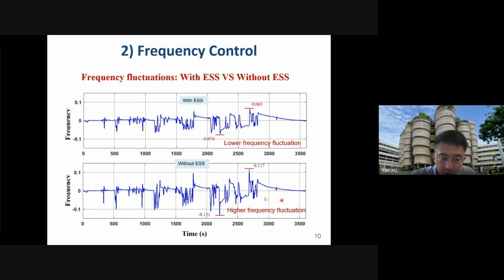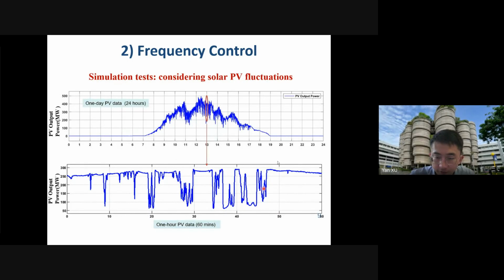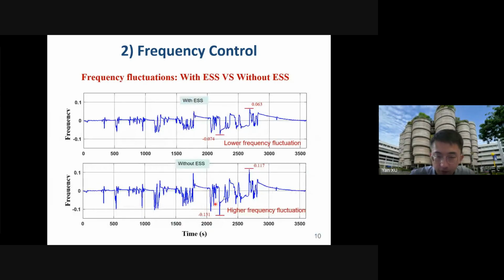Let me show the corresponding frequency of the system fluctuation due to the energy storage and the solar power output. Here in the bottom window is the original frequency over 1 hour. You can see the frequency fluctuates significantly, especially during the period of large solar power fluctuation. The highest and lowest frequency deviations are around minus 0.131 to 0.117. This is the original case without ESS.